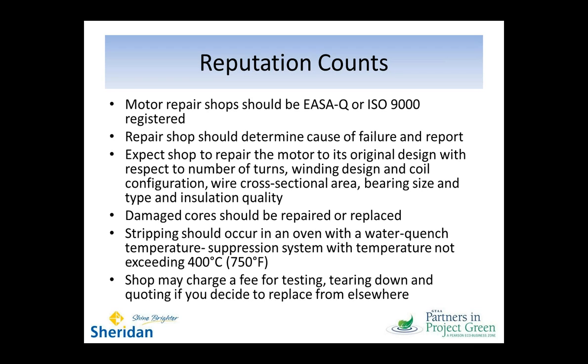You should be looking for international registrations. You should be expecting your shop to tell you about why the failure happened, give you a good report on that. And the expectation should certainly be that the shop is going to repair your motor to its original design. They should be able to repair or replace damaged cores. And this note about stripping occurring in an oven is that historically the insulation has been removed, the varnish has been removed from coils by dousing them in kerosene and lighting them on fire, which is really, really not good for the core of the motor, as you can imagine. So the idea is really to be gentle about getting these motors apart and putting them back together.